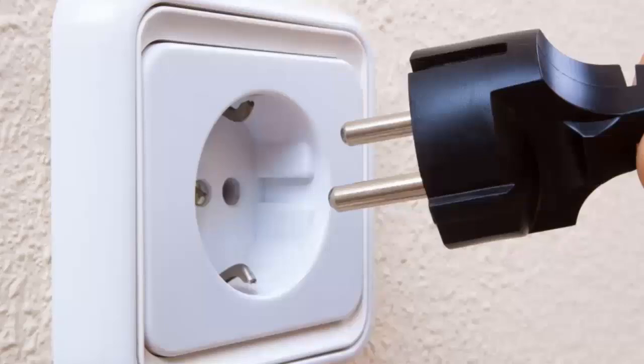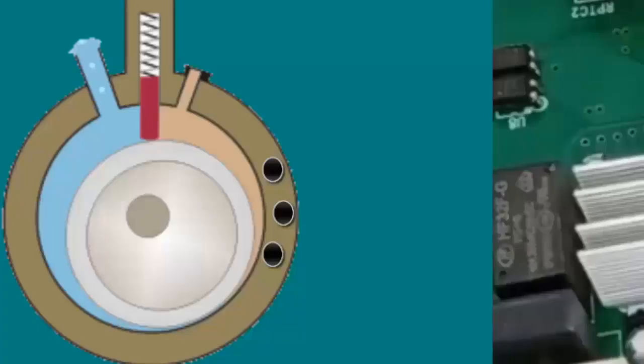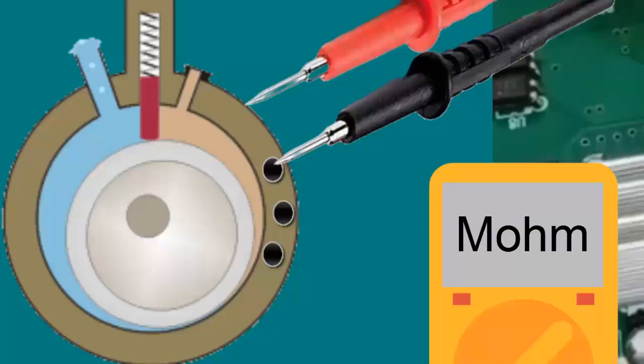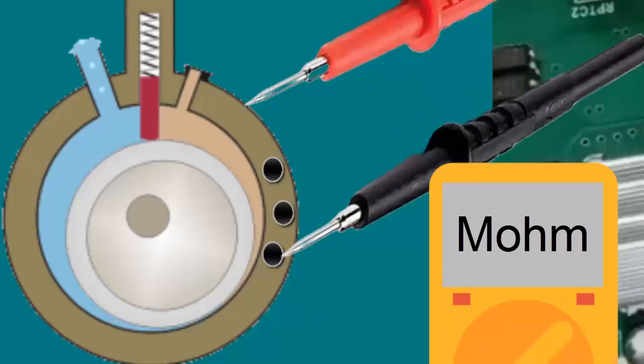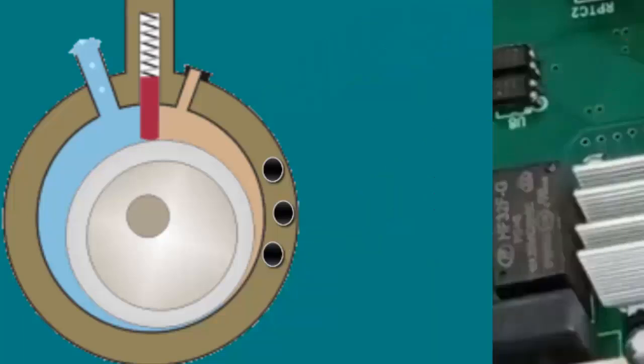C. Electrically disconnect the compressor from the electronic board, and with the help of a multimeter, check for very high resistance between any compressor connection pin and its casing. This ensures there is no current leakage to ground.